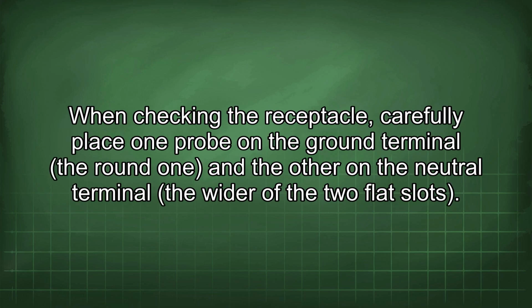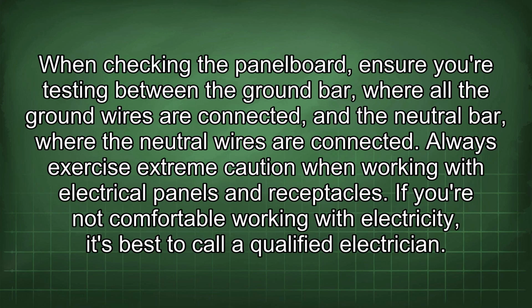When checking the receptacle, carefully place one probe on the ground terminal, the round one, and the other on the neutral terminal, the wider of the two flat slots. When checking the panel board, ensure you're testing between the ground bar, where all the ground wires are connected, and the neutral bar, where the neutral wires are connected. Always exercise extreme caution when working with electrical panels and receptacles. If you're not comfortable working with electricity, it's best to call a qualified electrician.